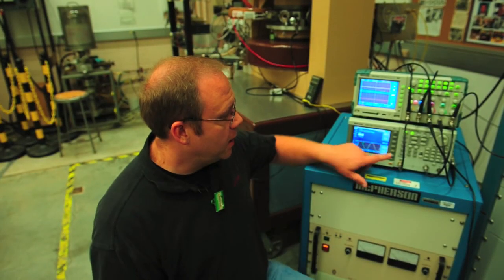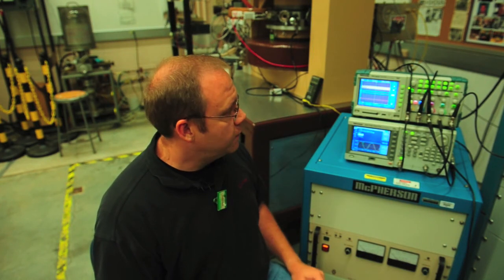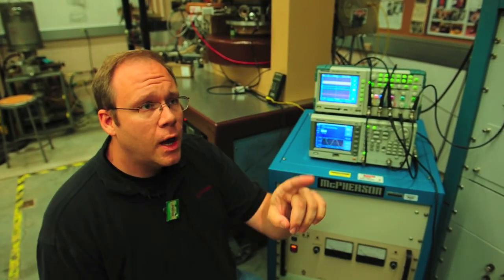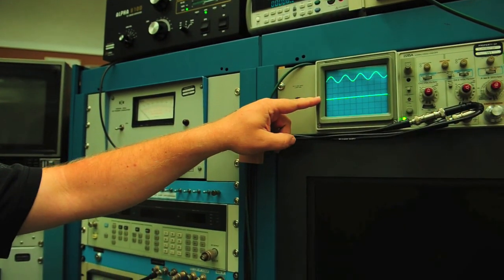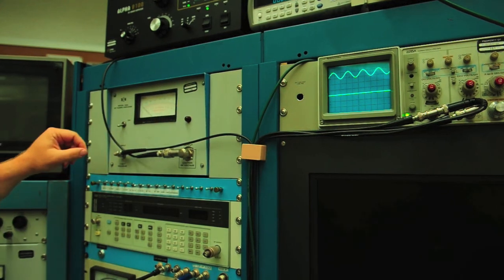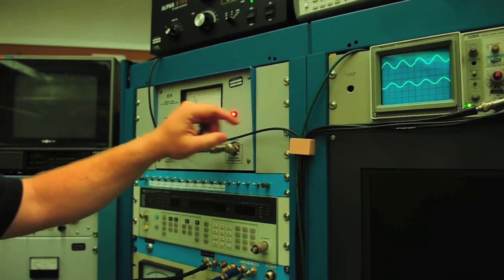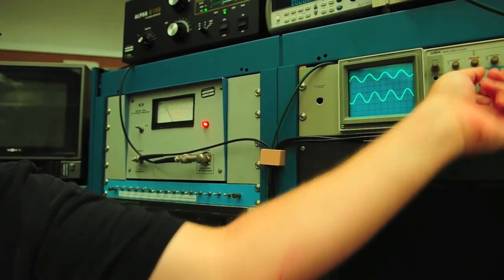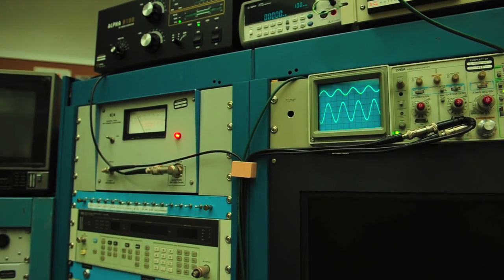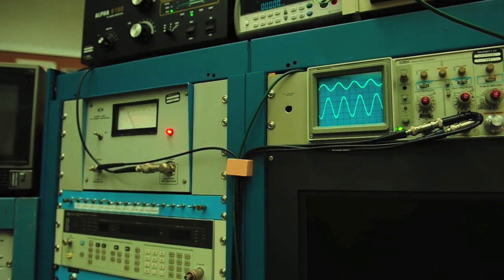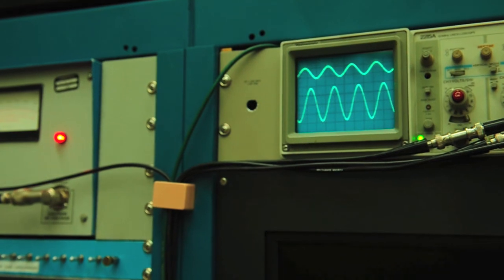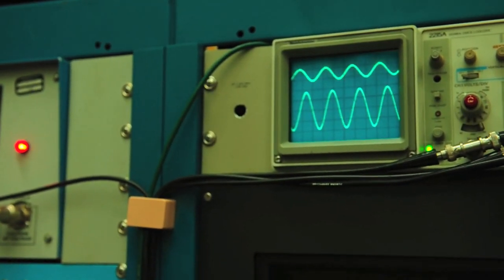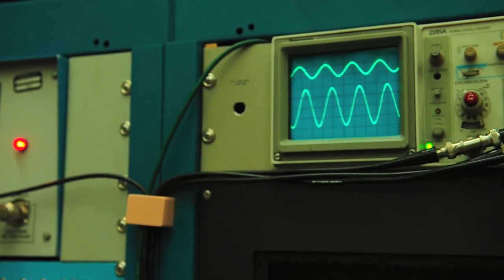So the first step in turning on the RF is to enable the low-level RF signal. We have 7.8 megahertz. We're plotting it on the upper trace of this oscilloscope, as well as the upper trace on this other oscilloscope. The bottom trace is the signal from the RF pickup in the chamber. So the first stage is to turn on the buffer amplifier. And we can see that we have a sine wave. We'll increase the vertical gain, so you can see that better. We'll go to the auto-tuner and adjust the capacitor on the chamber for maximum response. Now we are tuning the cyclotron tank circuit onto resonance, and we're doing this at a modest power of about 10 watts or so, so even if we did have a large reflected amount of power, it wouldn't cause any damage.